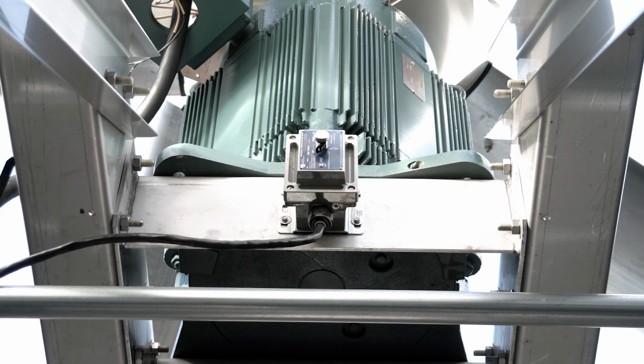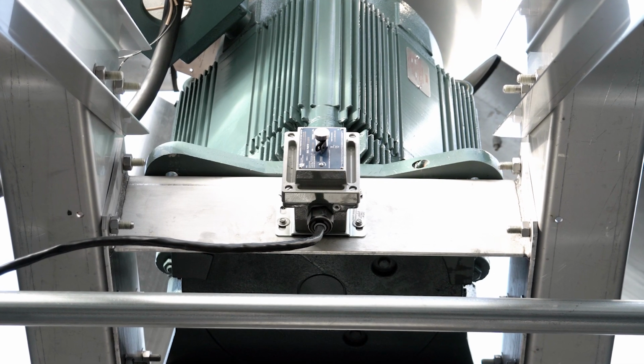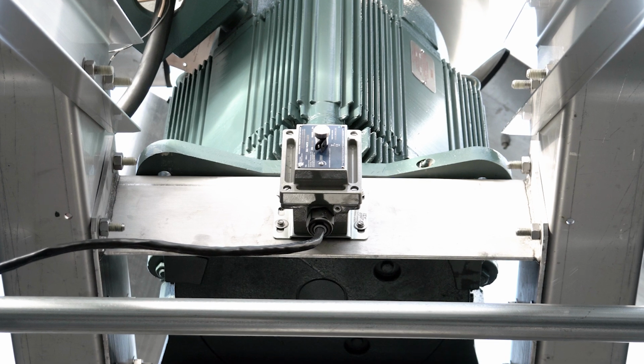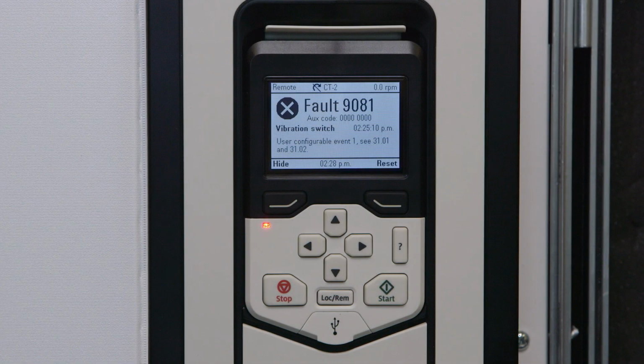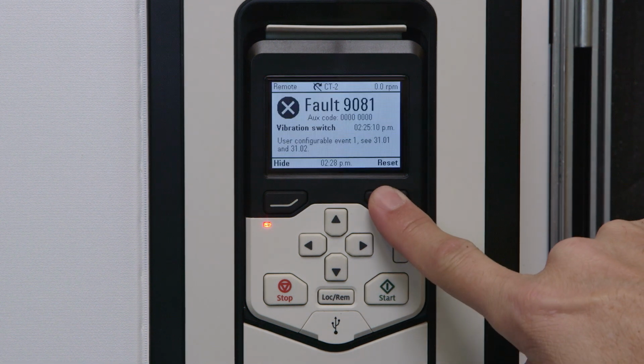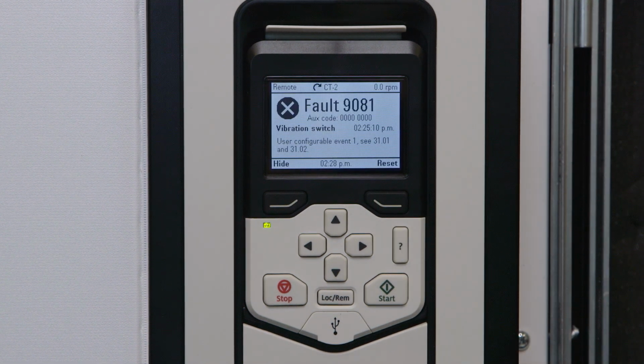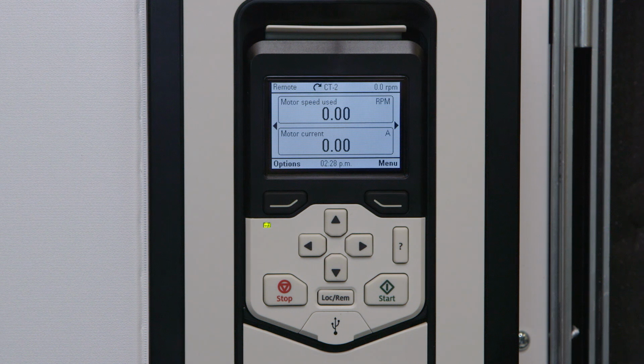To fix the vibration switch error, first manually reset the vibration switch at the tower. Then manually clear the fault at the VFD by pressing Reset on the VFD keypad. This should return the system to operation mode. If the fault cannot be reset, check the vibration switch wires XDI-6, labeled DI6, and XD24-4, labeled +24V. Ensure they are closed.